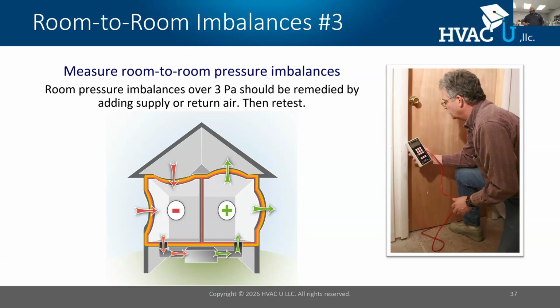And what we're looking for is anything over 3 pascals. If it's over 3 pascals, that lets me know that I have an unacceptable pressure differential. I have too much supply, not enough supply, too much return, not enough return. They're unbalanced. And if I'm unbalanced, I have some issues.